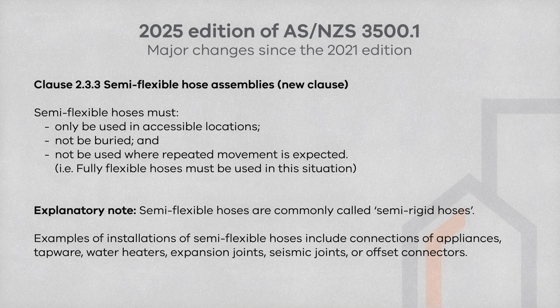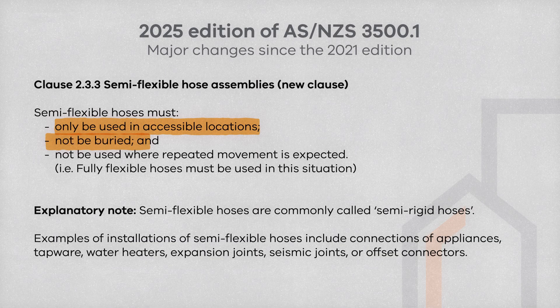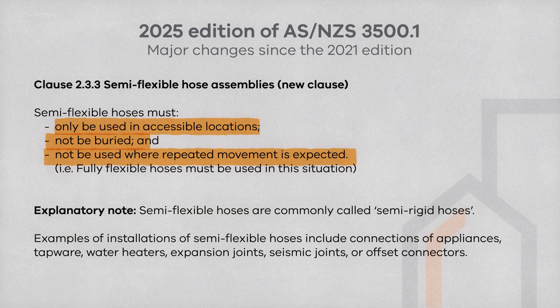Clause 2.3.3 is a new clause which expands on the requirements of semi-flexible hose assemblies. Similar to flexible hoses, semi-flexible hoses must only be used in accessible locations, must not be buried, and must not be used where there is expected repeated movement. Semi-flexible hoses are commonly called semi-rigid hoses. Examples of where these connections may occur include connections to appliances, tapware, and water heaters.